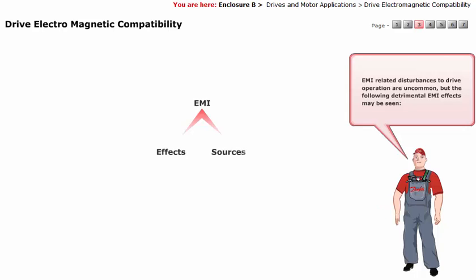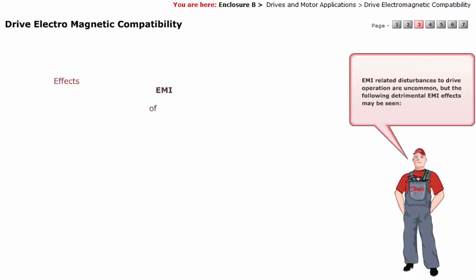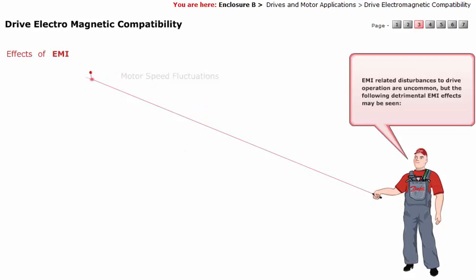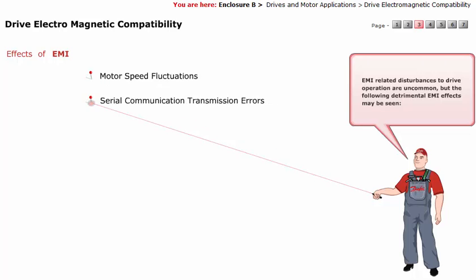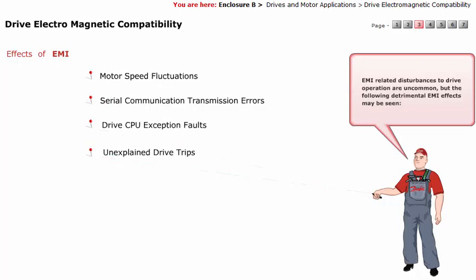EMI-related disturbances to drive operation are uncommon, but the following detrimental EMI effects may be seen: motor speed fluctuations, serial communication transmission errors, drive CPU exception faults, and unexplained drive trips.